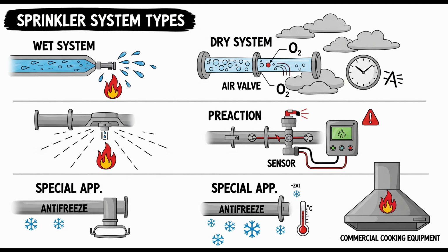Third is double interlock. In this type, water enters the piping only upon operation of both the detection devices and automatic sprinklers activating simultaneously. Both have to happen. Detector and sprinkler activation. Correct. Both conditions must be met to trip the main valve and allow water into the pipes. So double interlock seems specifically designed to absolutely minimize the chance of accidental water discharge. It is. Double interlock systems are the most common type used in those areas highly sensitive to accidental water damage. We talk about museums, data centers, critical archives, and often in cold storage, because they require two independent indications of a fire hot enough to activate detection and hot enough to open a sprinkler before water is introduced into the piping. Much lower risk of a false discharge from, say, a damaged detector or a physically damaged sprinkler head alone. Makes sense. Highest level of protection against accidental water release.